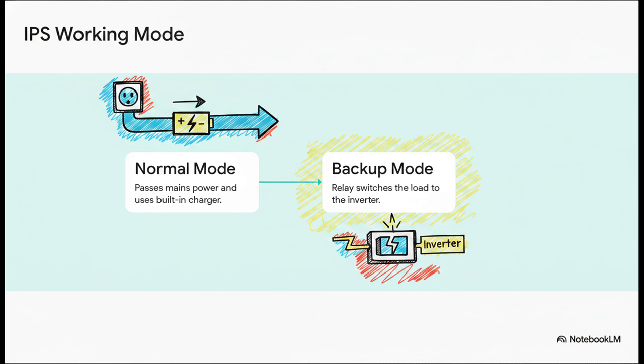It's basically a straight pipe. But in backup mode, when a complete power failure is detected, a mechanical relay physically switches the load over to the inverter. And you know, it's that physical mechanical relay switch that creates a critical difference in performance.